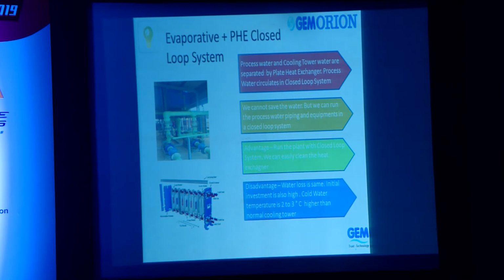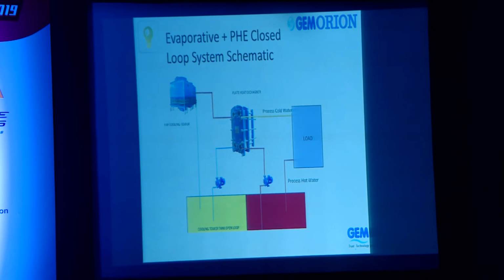Another system that can be adopted is a conventional cooling tower with a plate heat exchanger installed between the process and the cooling tower. That way these two circuits are separated and the process water is separated. So the machines are again getting protected. At the same time, your mother machines are protected, and the cooling tower exchanges heat through the heat exchanger. So we have an intermediate heat exchanger: the cooling tower water goes through one circuit of the plate heat exchanger, and the process water goes through the other circuit. We have adopted this system in many locations. A lot of customers have adopted it, like Nissan for their huge welding requirement. This is a standard process they follow. They isolate the machine's water from the cooling water. So here the water loss is the same, but at least the protection happens.